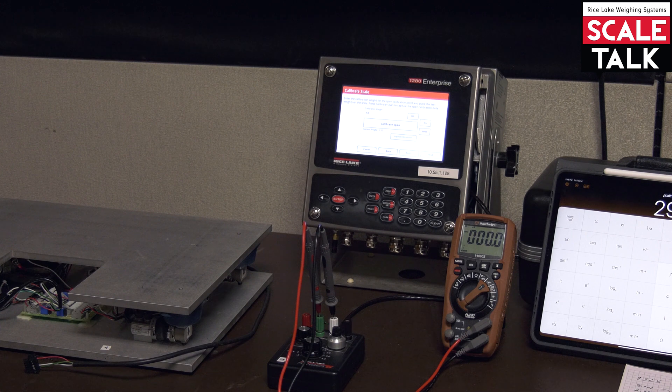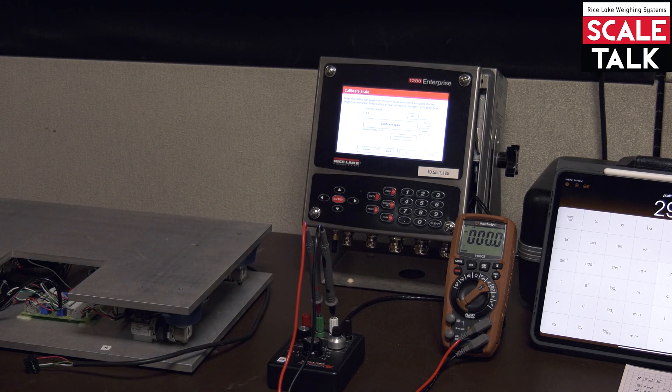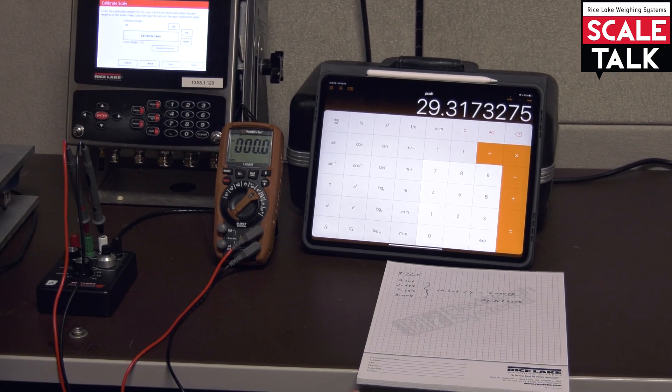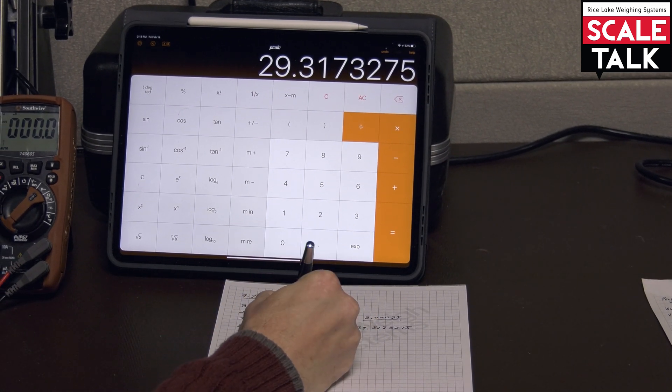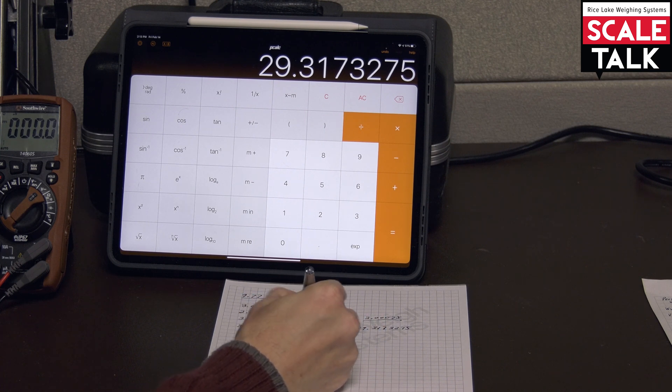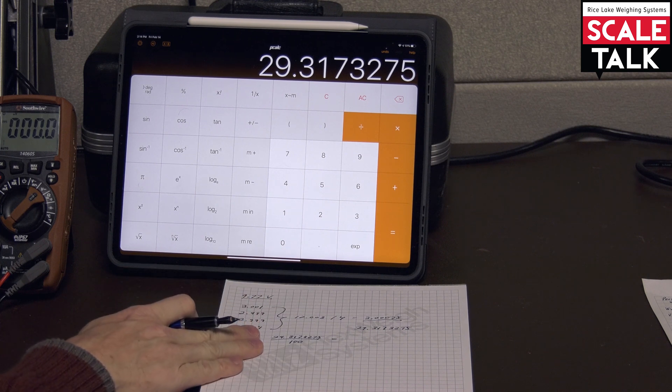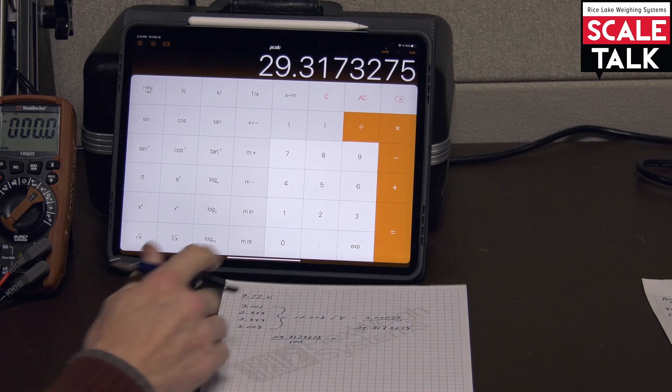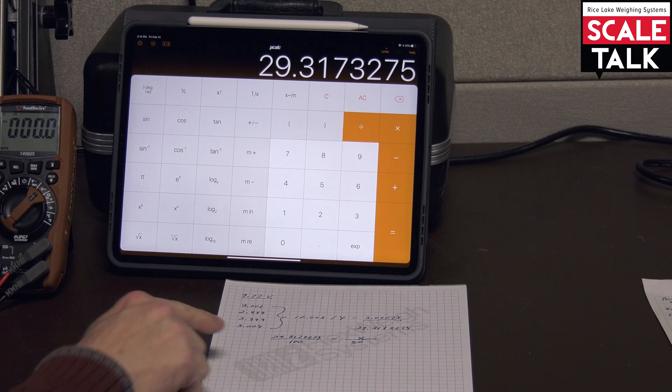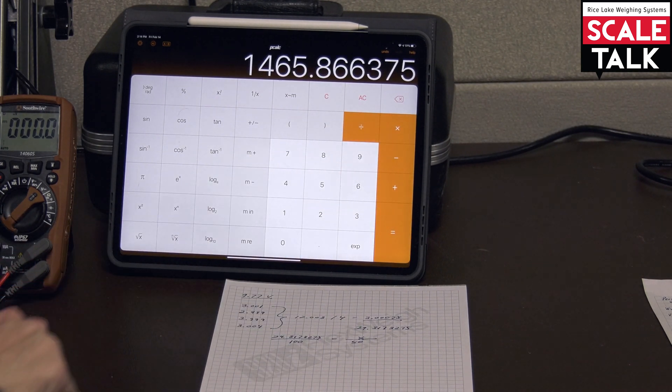And now we need to know well what would our millivolt per volt output be if we actually were putting 50 pounds on the scale. So that's where a little bit more math comes in here. So if we take a look at this we set up a small ratio where we cross multiply. Try to think back to algebra in high school. And we say that 29.3173275 if that corresponds with a full 100 pounds, remember that's the build, then that particular ratio needs to be the same as whatever that millivolt value is. We don't know what that is yet. So that's our variable, our x, related to 50 pounds. So what we're going to do is go ahead and cross multiply here. So we've got this 29.3173275 which is still on my display. We're going to go ahead and multiply that by 50.